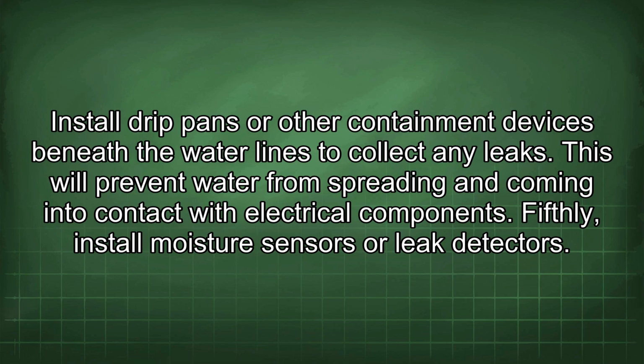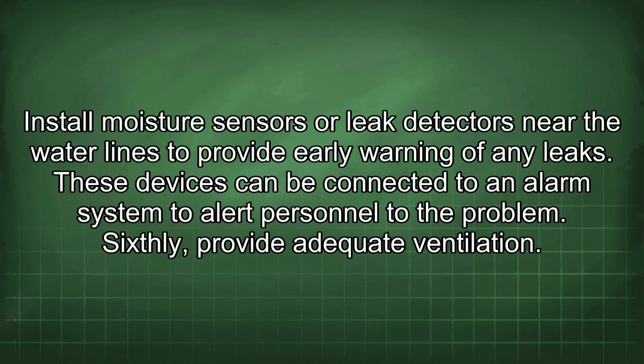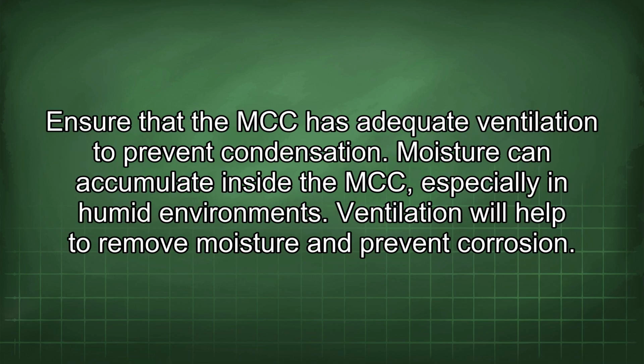Fifthly, install moisture sensors or leak detectors. Install moisture sensors or leak detectors near the water lines to provide early warning of any leaks. These devices can be connected to an alarm system to alert personnel to the problem. Sixthly, provide adequate ventilation. Ensure that the MCC has adequate ventilation to prevent condensation. Moisture can accumulate inside the MCC, especially in humid environments. Ventilation will help to remove moisture and prevent corrosion.